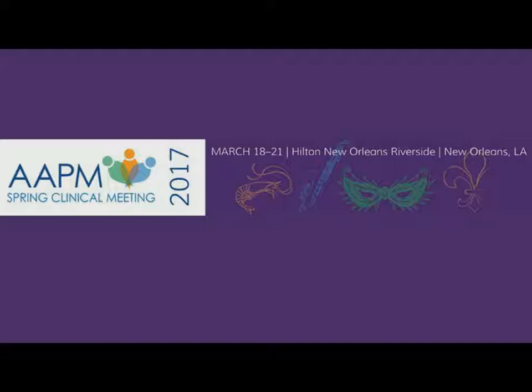I would exactly agree with you. I would hopefully not design a room to a minimum size. You really need that extra space to put all that extra tracking equipment in there. Most of the vendors, both Elekta and Varian, will give you recommendations for bigger rooms, but what they spec out is the minimum, and you really don't want to build that room to the minimum. So we've gone out on a limb in the VA and basically said that no room should be smaller than 24 feet in the longitudinal direction and 20 in the width. Yeah, 20 by 24 clear is pretty much the default minimum that you'd recommend for a room. Yeah.